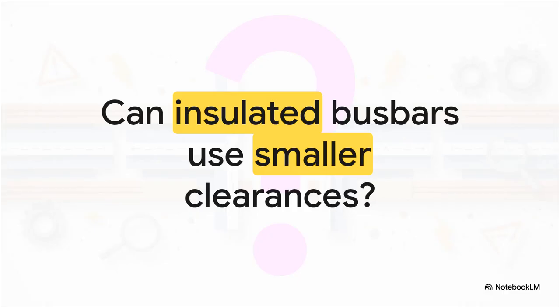Now, let's tackle a huge misconception head-on. Can insulated bus bars use smaller clearances than bare bus bars? Well, the answer is sometimes yes, but only, and I mean only, when the insulation system actually has validated dielectric capability. You absolutely cannot just slap a piece of shrink wrap sleeve on a bare conductor and decide you're going to ignore the air clearance logic. The difference between bare and insulated isn't just copper with a sleeve versus without. It's about verified dielectric performance across thermal and mechanical aging versus just hoping the air does its job. If your coating ages or cracks, your design instantly reverts back to bare busbar behavior.